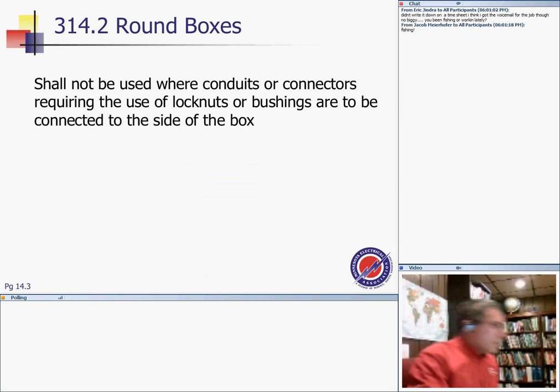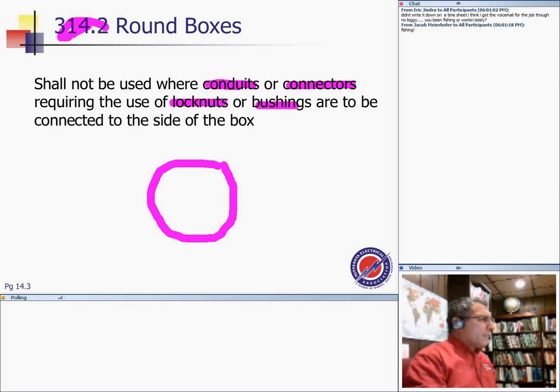Round boxes. This is in this article, guys. Very interesting. It says they should not be used where the conduit... Now we're using conduits or connectors that require the use of lock nuts or bushings to be connected to the side of the box. And with these round boxes, if you have a connector, it will not sit firmly on a round box. If you're looking for a conduit, lock nuts and so forth, it wouldn't sit firmly in a round box.